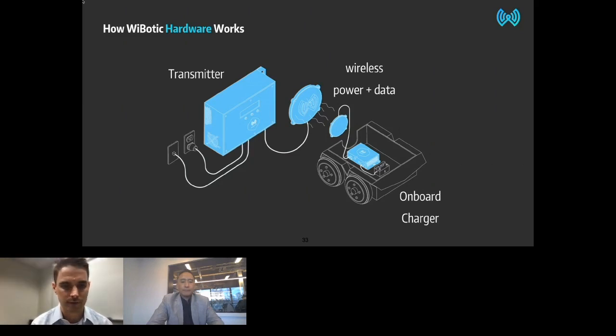Within the confines of the WiBotic system, you can select the battery chemistry. When you select lithium iron phosphate, for example, we have safety limits that prevent the charger from overcharging a battery. We will not charge if the voltage is below a certain threshold. There are provisions for that to be overruled if the BMS, for example, is intended to cut the voltage off and the voltage is supposed to be low because the battery needs to be recovered.